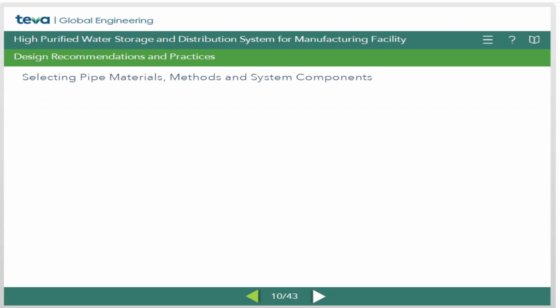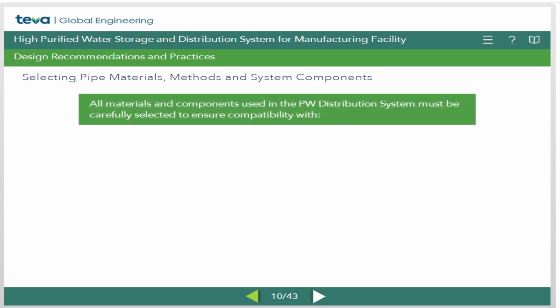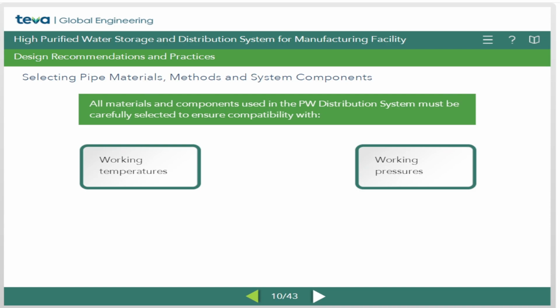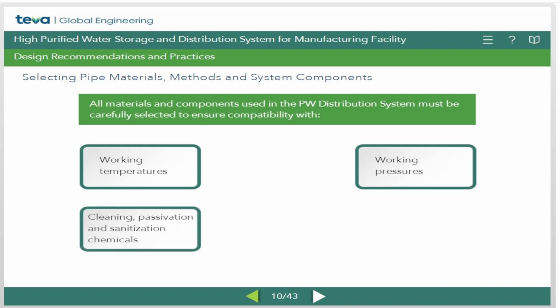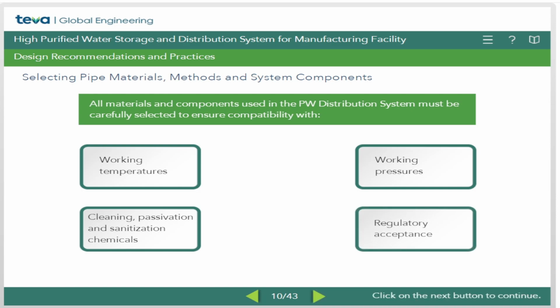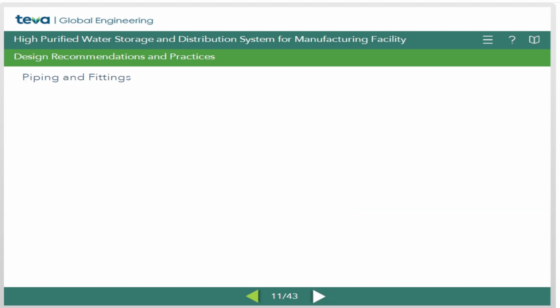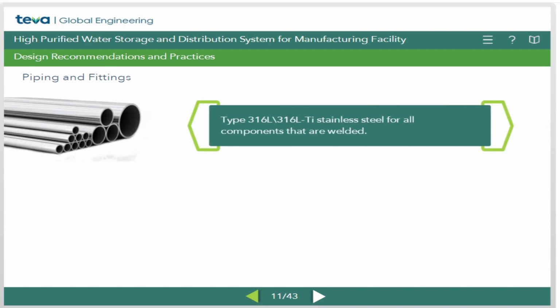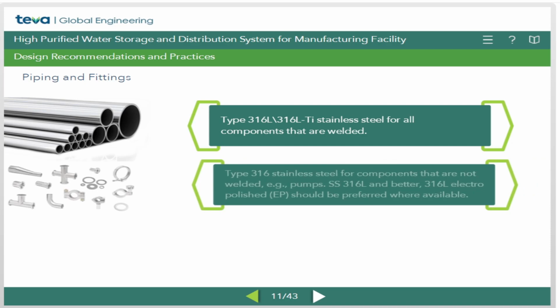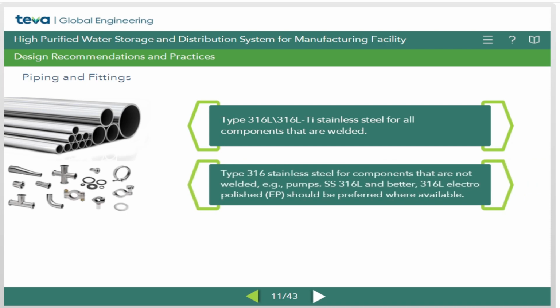Selecting pipe materials, methods, and system components. All materials and components used in the PW distribution system must be carefully selected to ensure compatibility with working temperatures, working pressures, cleaning, passivation, and sanitization chemicals, and regulatory acceptance. For piping and fitting, the following materials of construction should be selected: Type 316L or 316L-Ti stainless steel for all components that are welded. Type 316 stainless steel for components that are not welded.